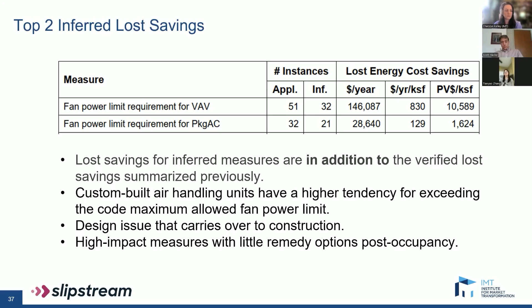There does appear to be a pretty high non-compliance rate for this measure based on plan review alone, and there's a good chance this non-compliance carried over from design to construction. Because of that, we feel more confident in the loss savings implications from these two inferred measures. These are high impact measures with little remedy post-occupancy, so it's important to get right the first time. Note that the loss savings for these two inferred measures are not included in any of the summary tables I went through previously, which reinforces that our total final results are conservative estimates.